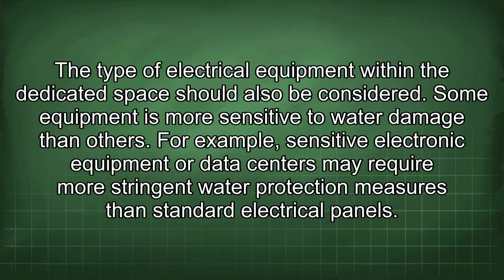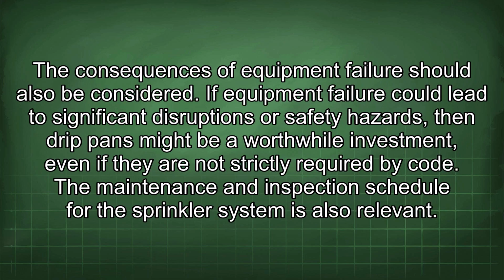The type of electrical equipment within the dedicated space should also be considered. Some equipment is more sensitive to water damage than others. For example, sensitive electronic equipment or data centers may require more stringent water protection measures than standard electrical panels. The consequences of equipment failure should also be considered. If equipment failure could lead to significant disruptions or safety hazards, then drip pans might be a worthwhile investment, even if they are not strictly required by code.